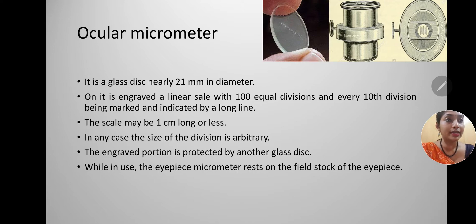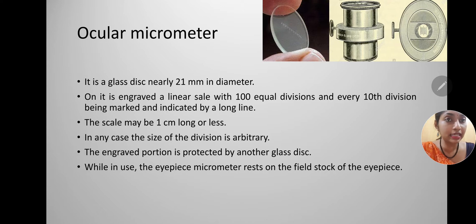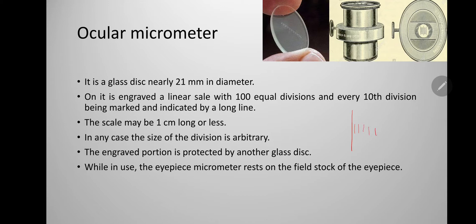The ocular micrometer is a round disc with etchings that is placed inside the eyepiece. The eyepiece must be taken out, the assembly removed, the ocular micrometer placed inside and locked, then placed back into the microscope. It is a glass disc approximately 21 mm in diameter with a linear scale of 100 equal divisions engraved on it. Every 10th division is marked with a long line. The scale is one centimeter long or less, and the engraved portion is protected by another glass disc.